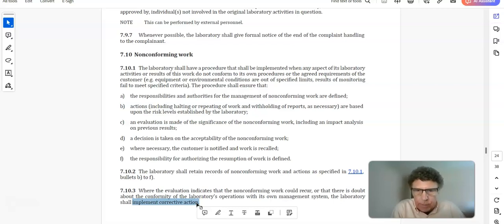No big deal. I mean, this kind of stuff happens. Septums get old, they have holes in them, big old gaping holes, and that introduces air into the GC and it can cause a bad baseline. So my nonconforming work is I got a bad baseline, cause is bad septum, correction, replace septum. Okay, end of story. I'm assuming the septum's bad for whatever reason. But then the next day, I'm walking through the lab and I notice an analyst doing exactly the same thing I did yesterday, right?